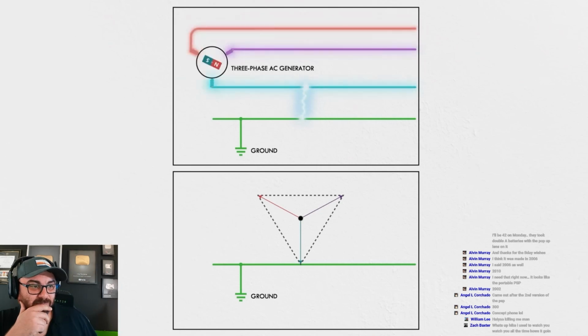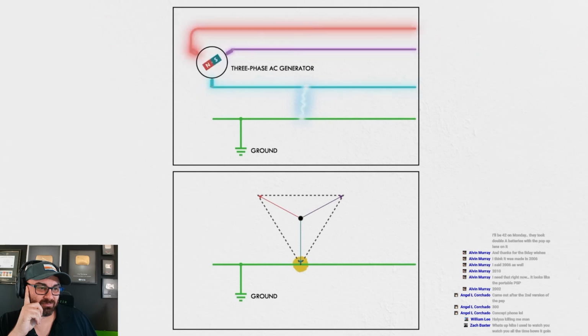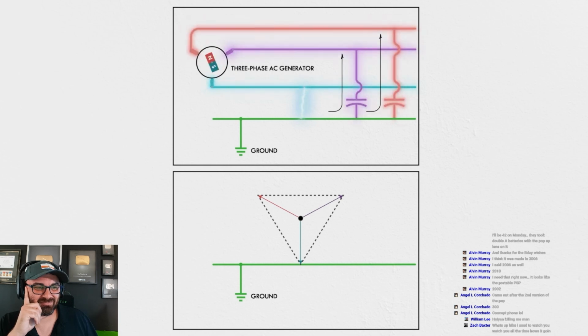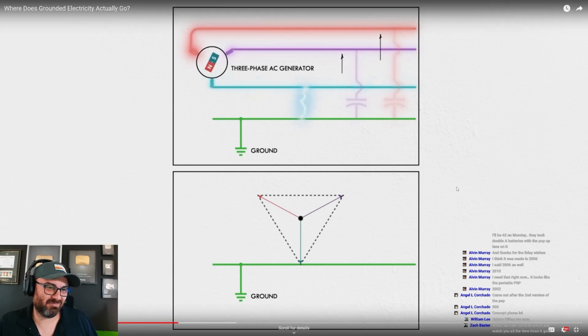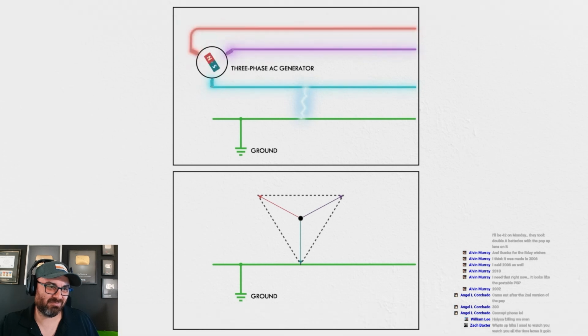Look back at our diagram and you can see the faulted phase potential is equal to ground potential. In other words, their difference is zero. There's no voltage, and when you have zero voltage, you also have zero current. No electricity is flowing from the conductor into the ground, or at least not very much is. You still have the capacitive coupling between the unfaulted conductors that allows a little bit of current to flow, but it's not much. And that matters because nearly all the devices that would protect a system from a problem, like a ground fault, need some current to flow.